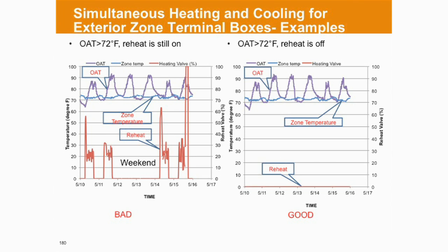So you're saying in the second graph that your CFM into that zone probably is lower than in the first graph? Yeah. So that graph might be better if it had the CFM also on it, so they can compare the two? Just so, but that's what the situation is here, because otherwise there's no difference in the graph, and it's showing that you're going to keep your zone temperature without having any reheat. So that's missing from this diagram. You mean the CFM? Yes. I didn't show the CFM. Right. Yes, that's a good comment, because if we plot CFM here, the left-hand side CFM is much higher than the right-hand side. That's very good comments. If we show that, that can give the whole picture to the audience.